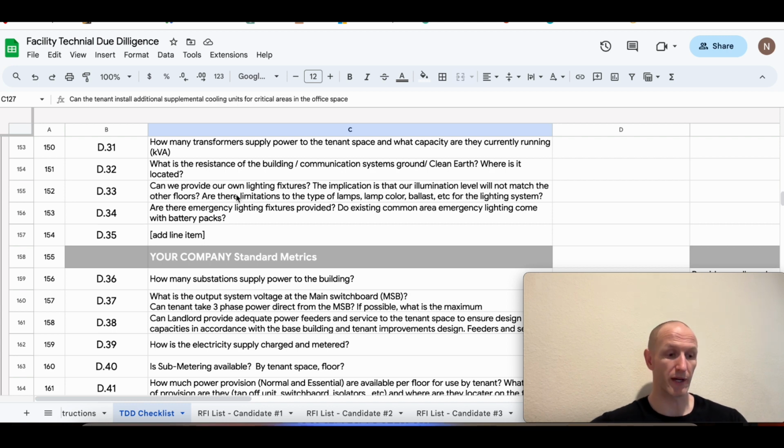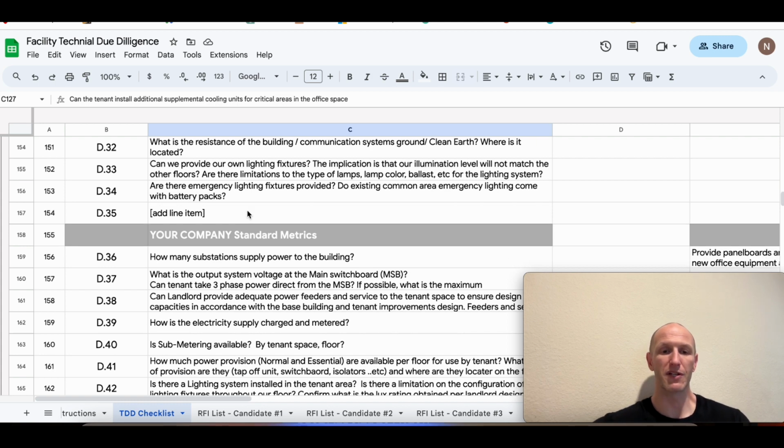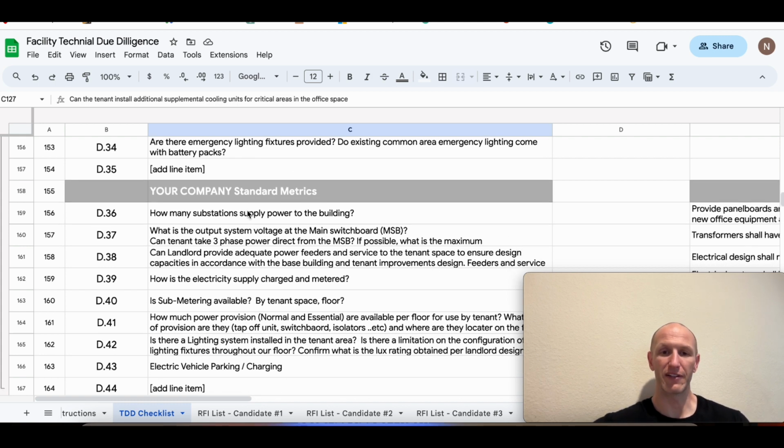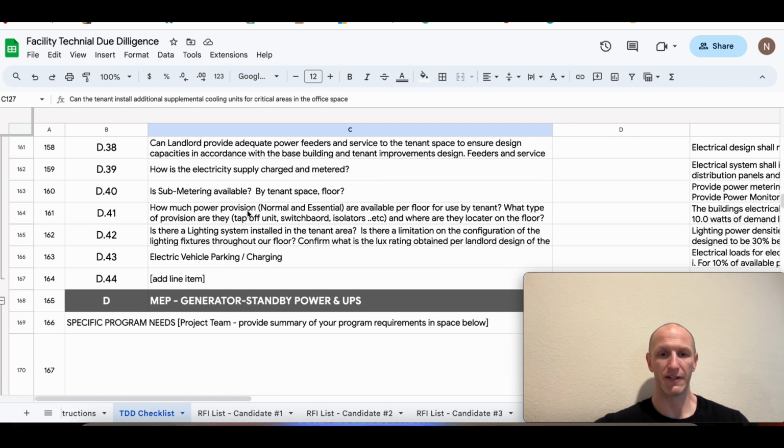I had a building one time, actually I had multiple buildings. A coordination study wasn't done. They continued to add on tons of electrical equipment. Next thing you know, it skips the standard path of coordination and ends up shorting out a bus duct. We lost power to the building, a full building, right at the end of the winter, which was the peak season. It cost hundreds of thousands of dollars in room compensation. I'm sure you get the idea. So having that done is so imperative.